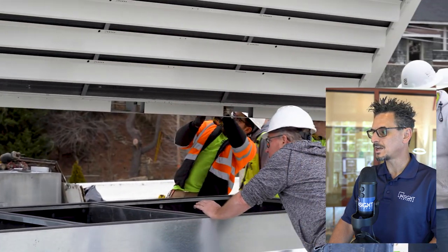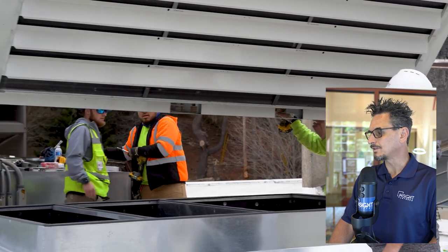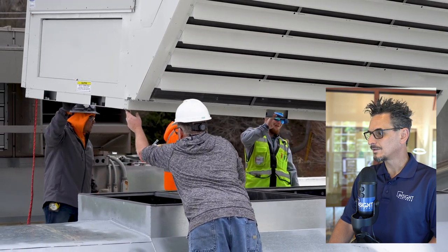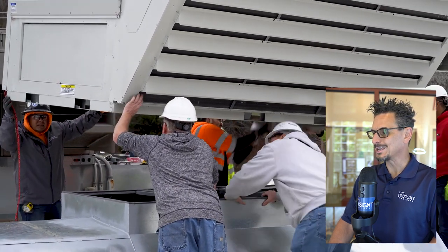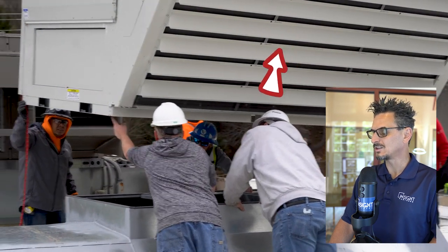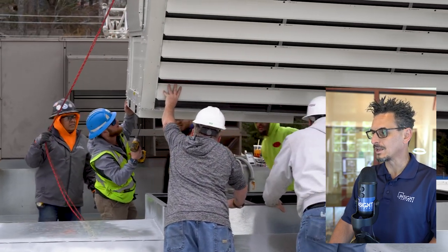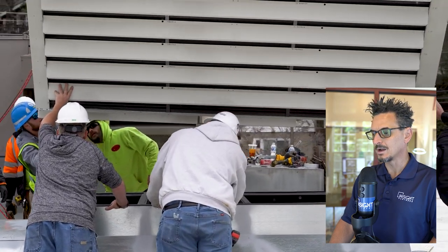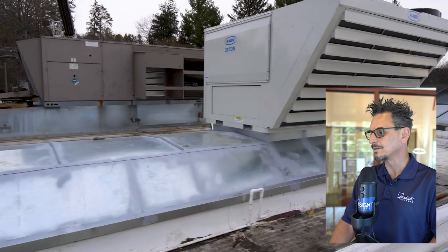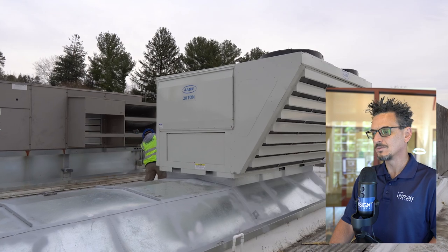You see the guys here just making some final checks with the dimensions, making sure it all evens up. Safely lowering this onto the adapter curb. You can see those are hail guards on the AAON unit there on the condenser coil. The condenser coil is slanted, so there is very little chance of hail getting in there to damage it. But the guards also act as protection for people walking around the roof, or tools or equipment that might bump into the condenser coil — so it's not a bad idea to have those, although we don't provide them very often.